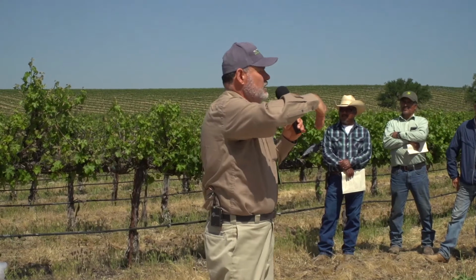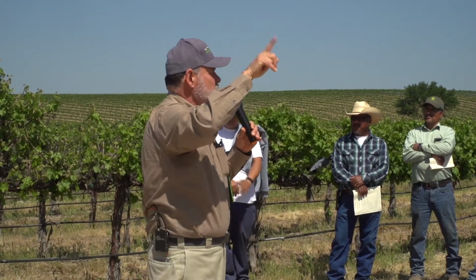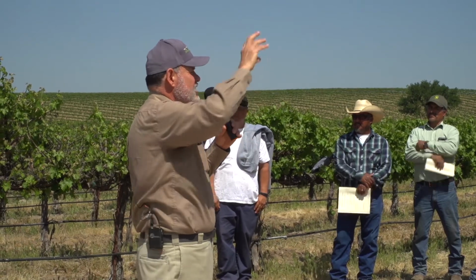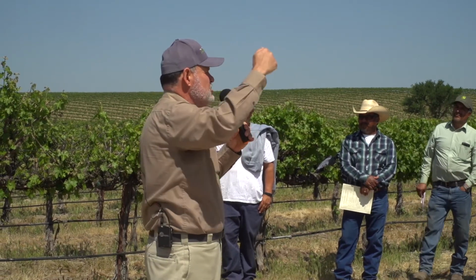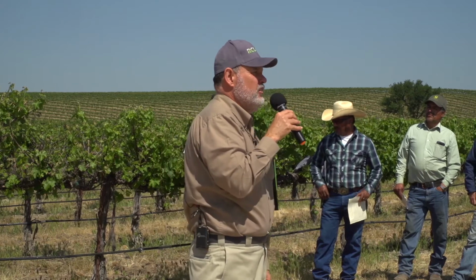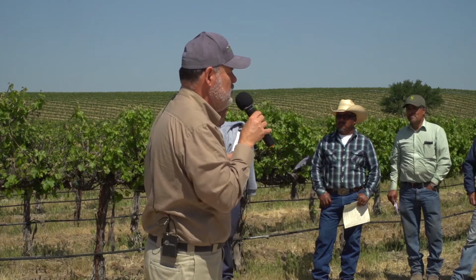Okay. They always want to have an air vent also, because it had the elbow going down. By design, at the highest point, the lowest point, anything that goes down, any of the high points, you want an air vent to get rid of the air. You don't want any air in the system.